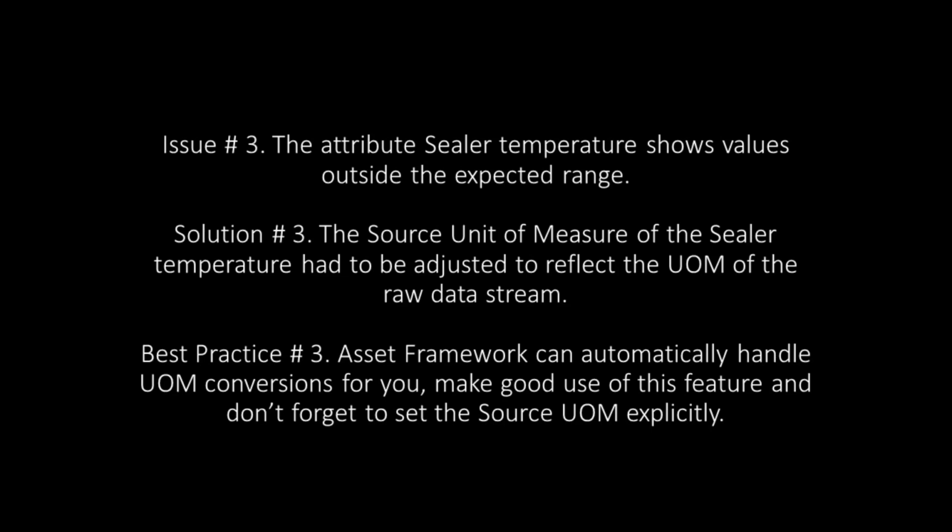Issue 3 was that the sealer temperature was showing values well outside the range. We were getting values between 40 and 60, and the expected range was supposed to be between 70 and 270. When we did our research, we found out that the devices were purchased in Europe and were calibrated to record temperature in Celsius. However, the default temperature in Asset Framework was Fahrenheit. So we set the source unit of measure on the sealer temperature attribute to be Celsius. That way, Asset Framework knew that it had to convert between Celsius and Fahrenheit.